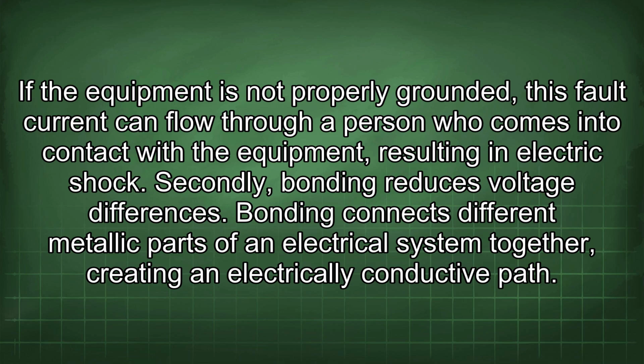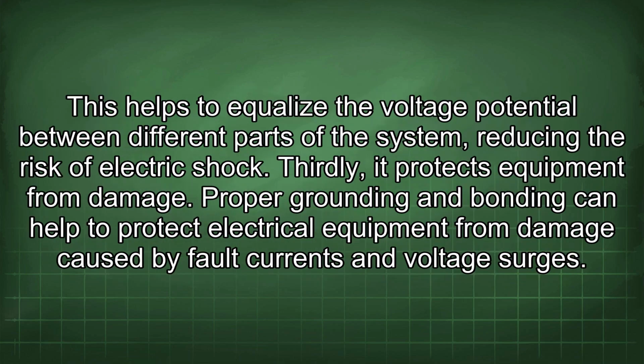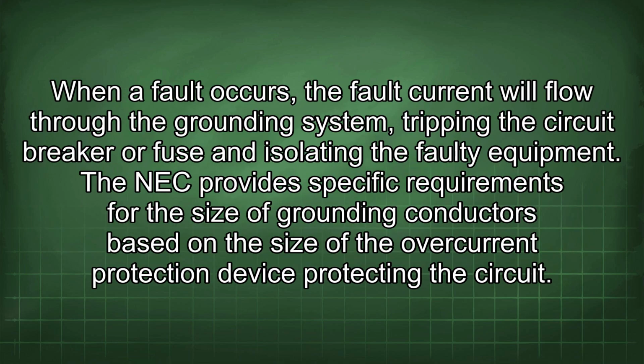Secondly, bonding reduces voltage differences. Bonding connects different metallic parts of an electrical system together, creating an electrically conductive path. This helps to equalize the voltage potential between different parts of the system, reducing the risk of electric shock. Thirdly, it protects equipment from damage. Proper grounding and bonding can help to protect electrical equipment from damage caused by fault currents and voltage surges.